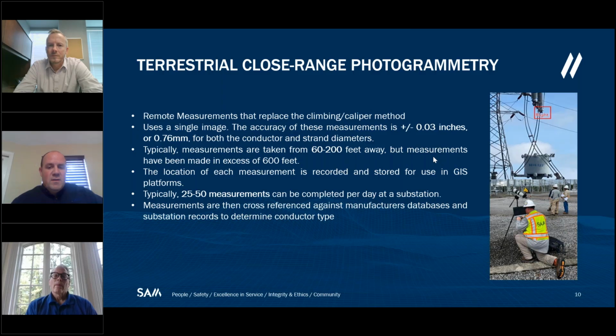Using the cameras that we have available, we can get an accuracy of plus or minus 0.03 of an inch for both the conductor and the strand diameters. Typically, like I said, we take them from 60 to 200 feet away, but we've made some in excess of 600 feet. And a single crew, really a one-person crew equipped, can do 25 to 50 measurements per day in a substation. So it's nearly as accurate as calipers. It's not, but it's almost as fast as visual verification.